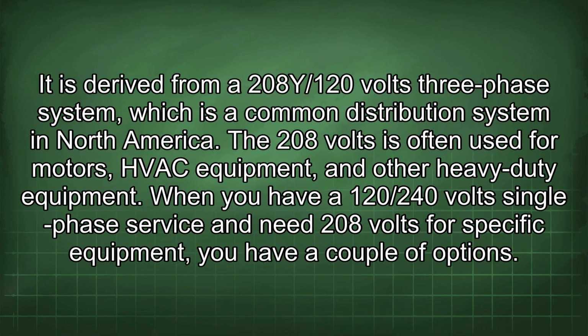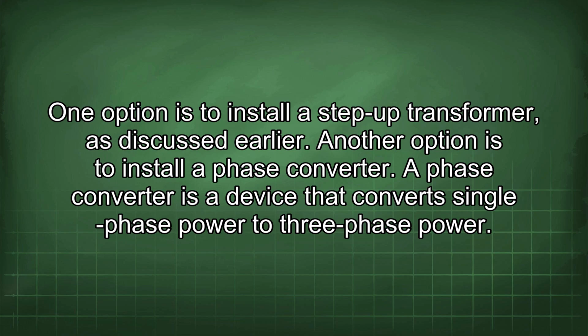It is derived from a 208Y/120 volt three-phase system, which is a common distribution system in North America. The 208 volts is often used for motors, HVAC equipment, and other heavy-duty equipment. When you have a 120/240 volt single-phase service and need 208 volts for specific equipment, you have a couple of options. One option is to install a step-up transformer, as discussed earlier.